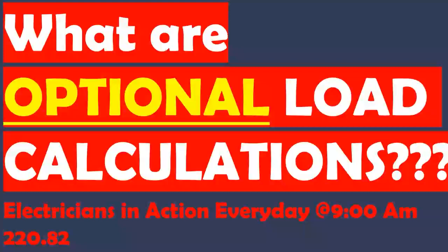Most inspectors — all of the ones I know personally — if they require you to do a load calculation, they're going to want you to use the standard method because that gives them a more accurate perception of what the load demand is really going to be. But the reason people love doing optional method load calculations out in the field is because it's easy. We take the nameplate of everything, we take the square foot, we apply one demand factor, and then we add the heating and cooling, and we're done.